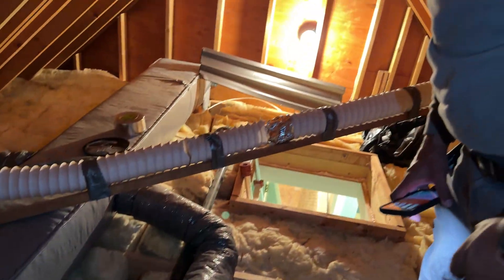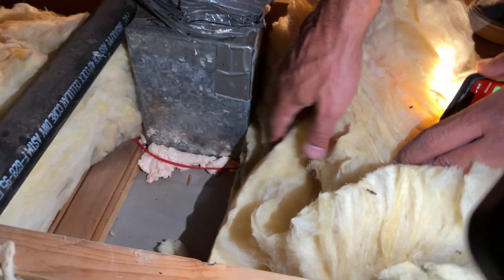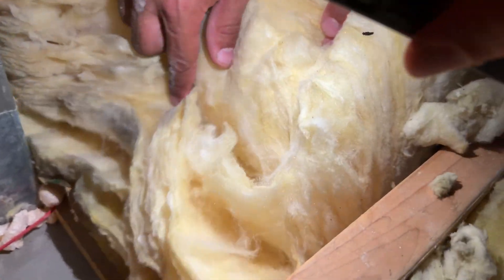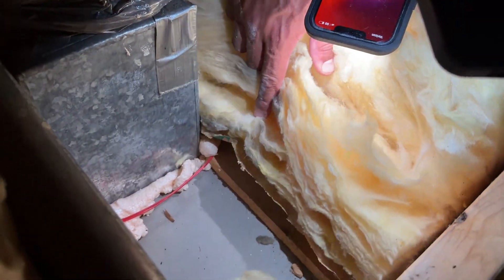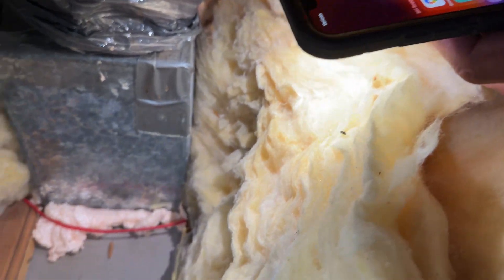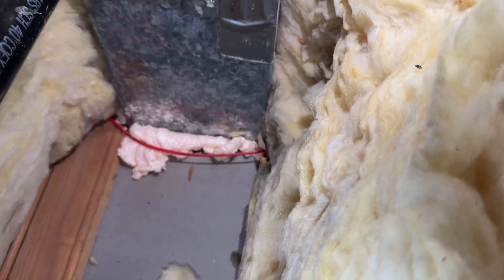Here's another example — you can see the black dust that builds up on the fibers coming from the penetration around the ductwork. It's light because the insulation was moved around, but this is showing that top area not being sealed properly — it's a leak around the ductwork penetration. The air leaking out leaves dust traces, so sealing it is standard practice.